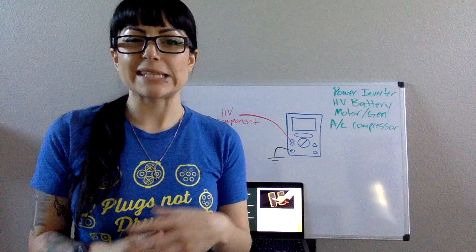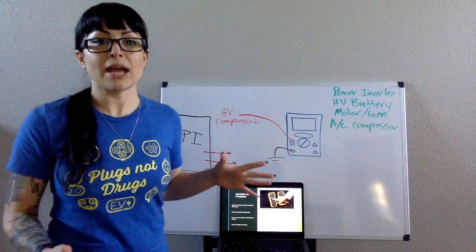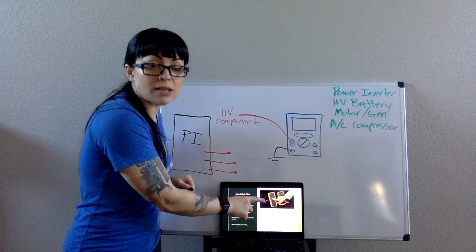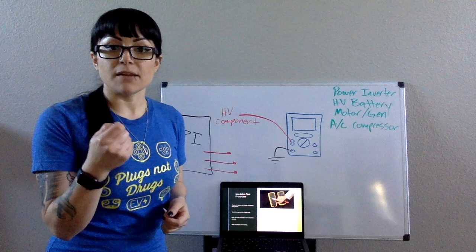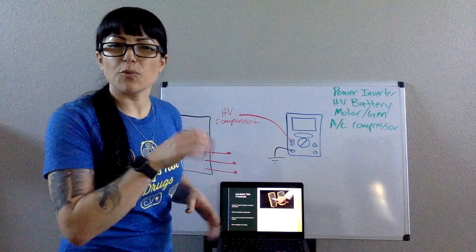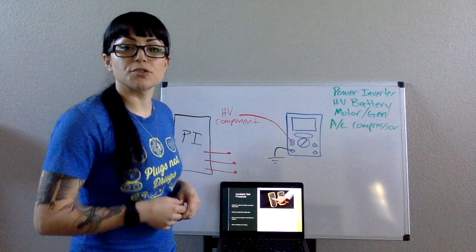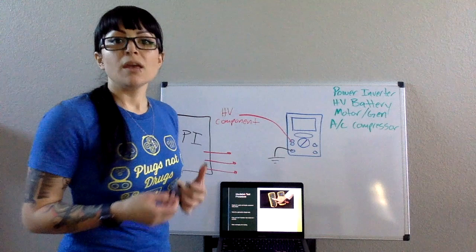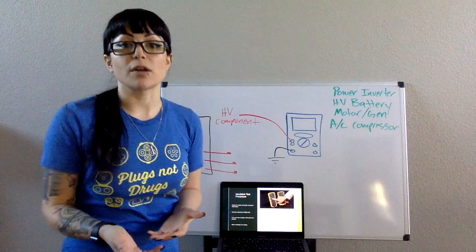Let's talk a little bit more about - okay, I've connected it, what do I do next? Once you've connected it, you're going to press - in the picture here, the gentleman is pressing a large orange button. They make leads that have a button inside of it. I'll show you guys how to use those when we get back to lab. When you touch it and you're ready to test, you are going to press that button for at least two seconds, give it a chance to send that voltage through. Within two seconds, you should have a reading up on your meter. That reading is going to tell you whether or not that component is the isolation fault or you need to move on and test something else.